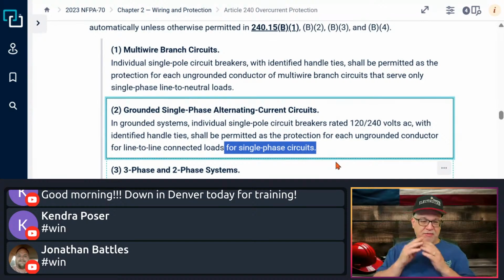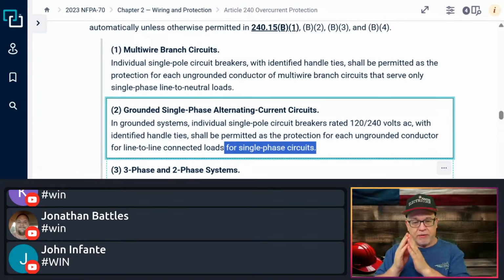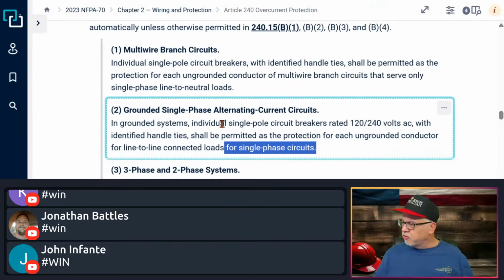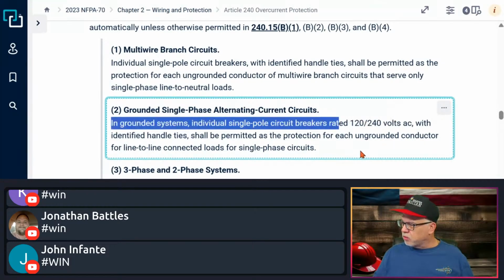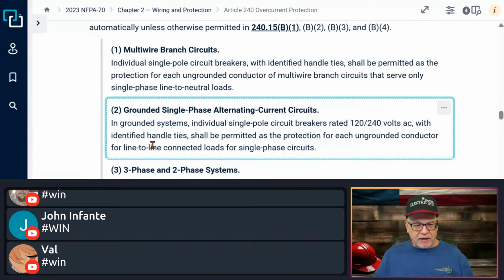Okay, so you can have a line-to-line. I can use two individual single poles, as long as they're rated 120/240. Each one is rated 120 to ground, and then of course it's also rated line-to-line 240. So that is the slash rated breaker. It's a 120/240, not a straight rated, just one voltage. It's a slash rated. So as long as it's individual single pole breakers or slash rated 120/240, and they have an identified handle tie, then I could use two single poles.